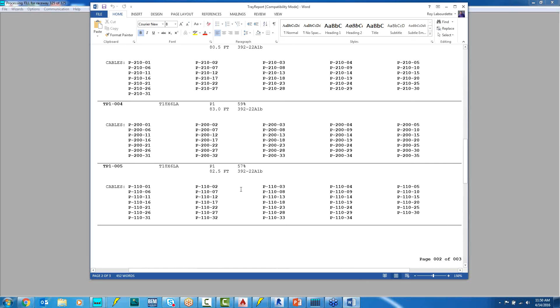So if we were to get to an 80% fill percentage, because I've got a 20% reserve, the program will not go ahead and continue to add cables to that particular raceway. It will look for another raceway, or it will give you an error that says that it could not find a route.